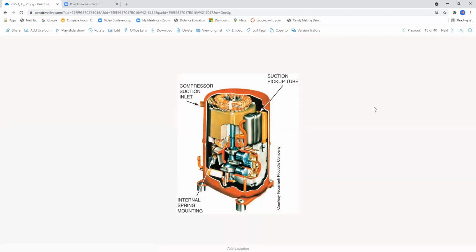Okay, this is the internals of a hermetic compressor that you would see in a lot of AC refrigeration systems. Notice that you have your motor winding up here, your suction pickup tube up here, and your internal spring mounts to keep this thing isolated. I've actually seen these springs break because of liquid refrigerant coming in here. When they break, these windings sometimes have a tendency to ground out against the, I would call this the pot or the panel that covers the hermetic unit. Typically, this is a 2-piece construction, bottom and top shell, and of course they're welded right here in the middle.